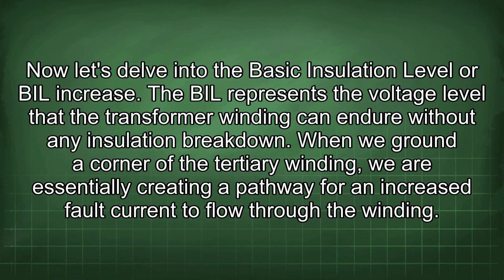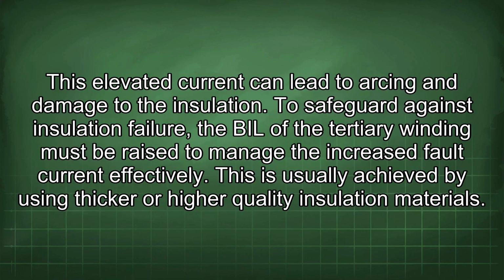phases. Now let's delve into the basic insulation level or BIL increase. The BIL represents the voltage level that the transformer winding can endure without any insulation breakdown. When we ground a corner of the tertiary winding, we are essentially creating a pathway for an increased fault current to flow through the winding. This elevated current can lead to arcing and damage to the insulation. To safeguard against insulation failure, the BIL of the tertiary winding must be raised to manage the increased fault current effectively. This is usually achieved by using thicker or high-quality insulation materials.